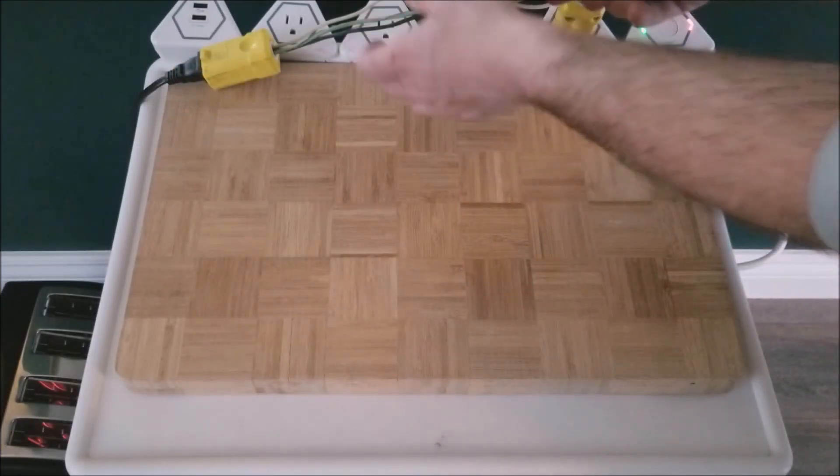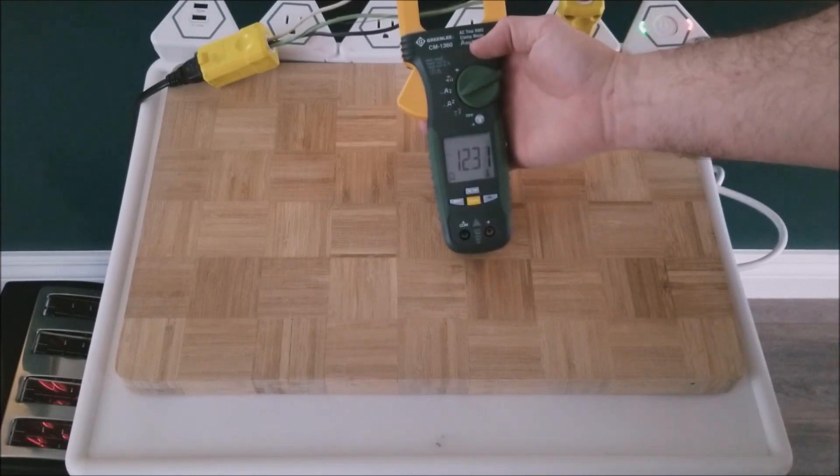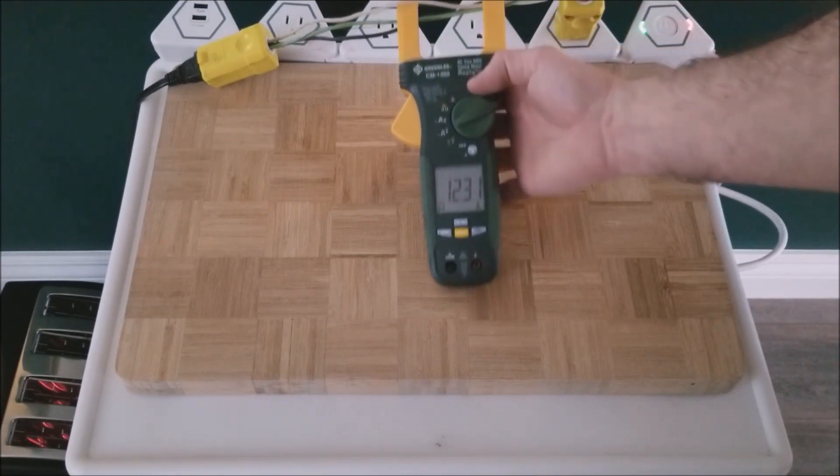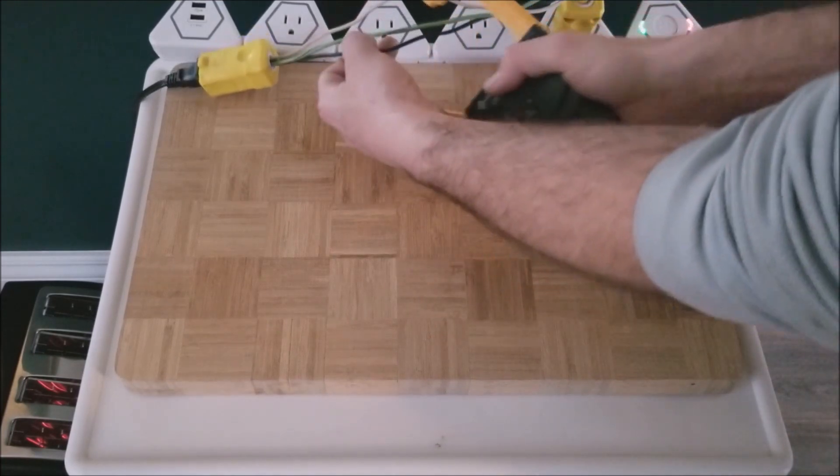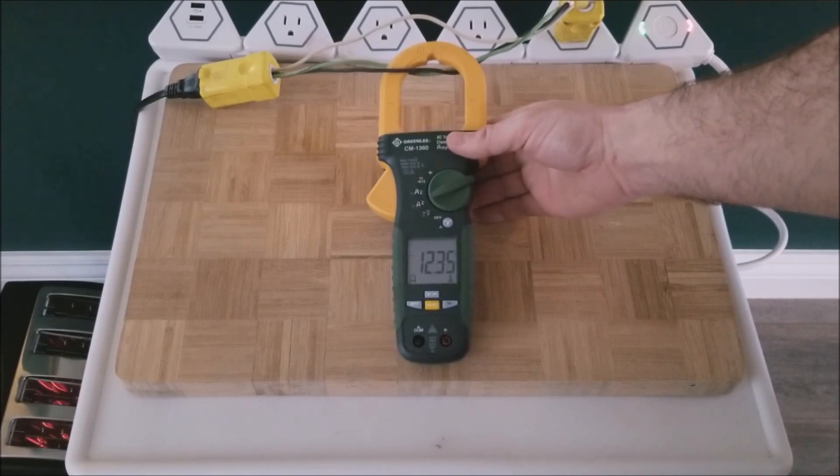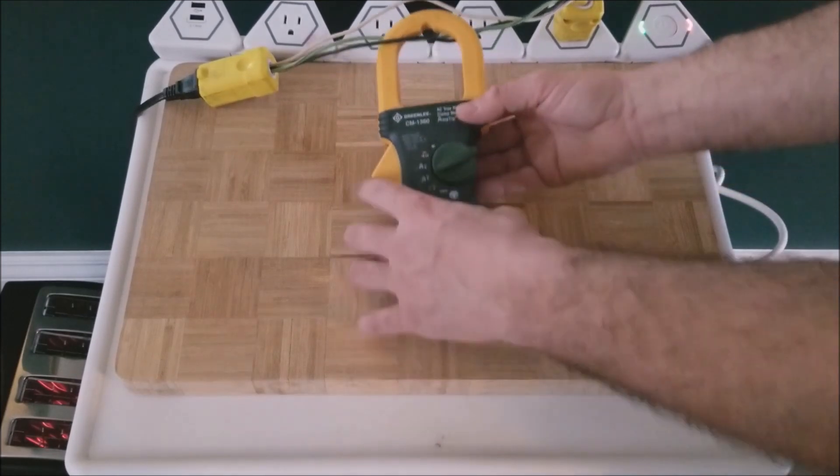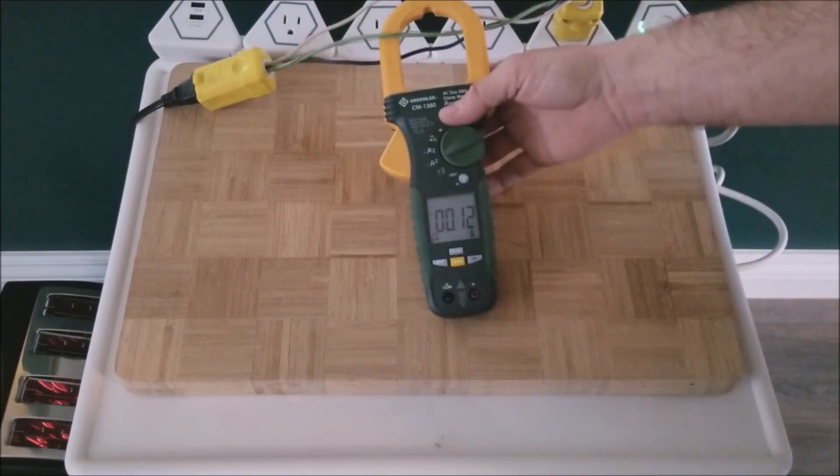So the first thing I'm going to show you is extremely important. Now what I'm clipped onto here isn't actually the live wire, it's the neutral wire. And as you can see, we're still conducting the entire 12 amps, same as the live wire. I'm not going to get into why that is, but it's important that you know the neutral wire is just as dangerous as the live wires.